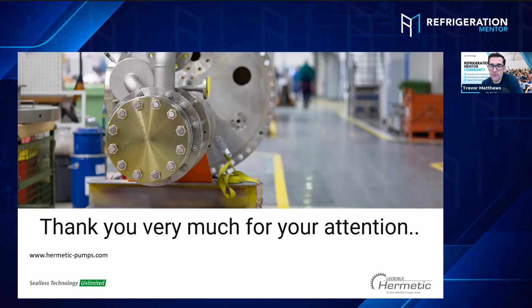So we got a few in here. Darwin says a very important feature in a pump illustration is that the flat on top eccentric reducer avoids air pockets that will cause cavitation. Moreover, long radius is better due to low pressure drop compared to short radius. 100%, I agree with that.